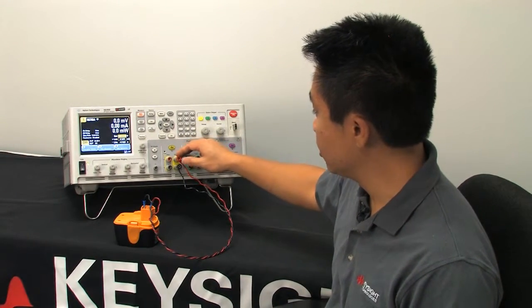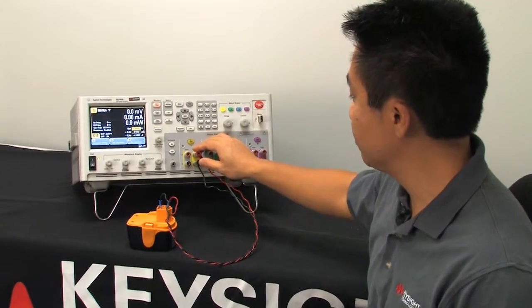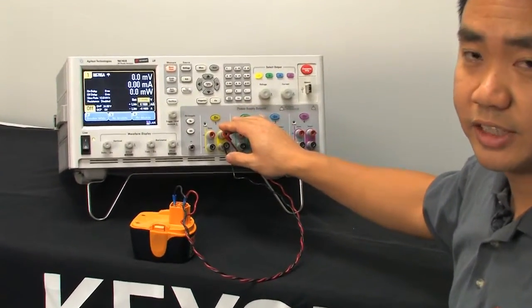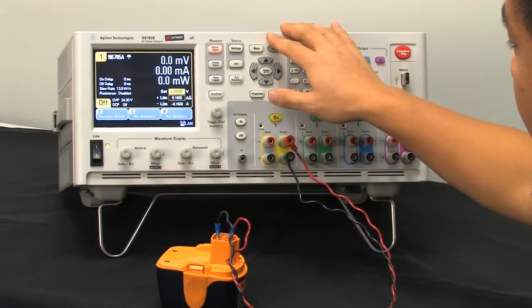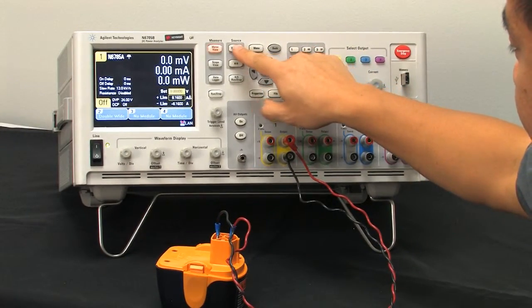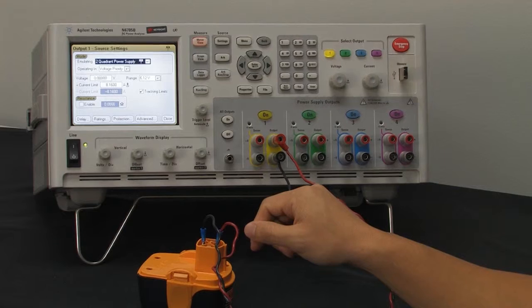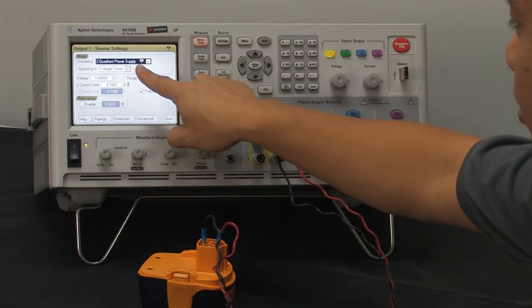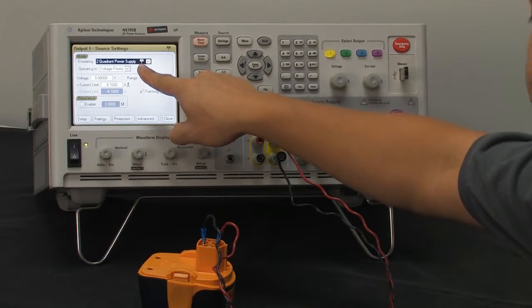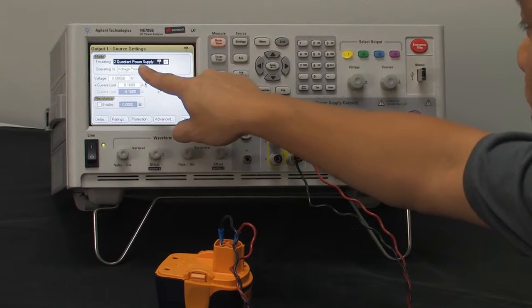So let's go ahead and go to the front panel here and we'll set up the source measure unit to act as an electronic load. The first thing we're going to do is press the settings button. By default, the emulating mode on all SMUs as it comes up is always two quadrant power supply.